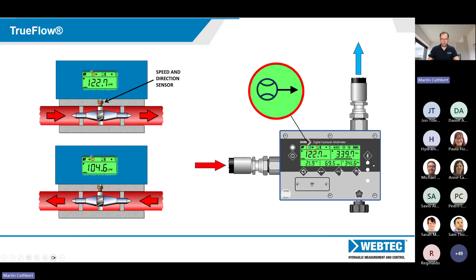As you can see on here, we've got an arrow to the right and an arrow to the left. And as Steve demonstrated, that's available. That information transfers onto the mobile phone as well. So if we look at the inside of the tester, just a little schematic, we've got the digital flow meter, a digital temperature sensor and a digital pressure gauge. We've got a little shuttle valve here, so that it's always seeing the high side of the pressure, irrespective of whether you're using it from left to right or right to left. We've got the loading valve here to restrict the flow and to raise the pressure. And then we've got a bypass system here with two burst discs, which form the Interpass system, which will rupture in the event of overpressurization.